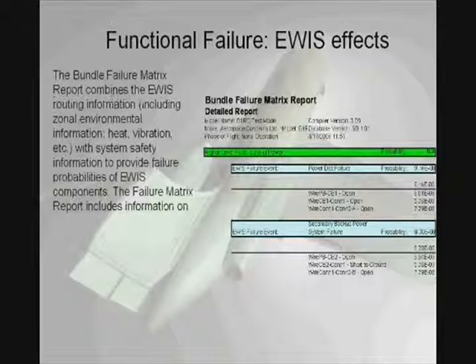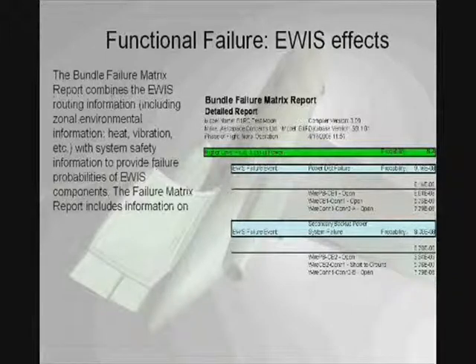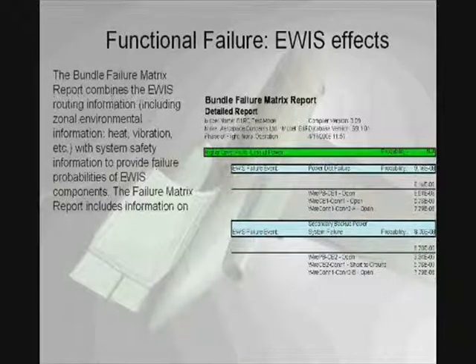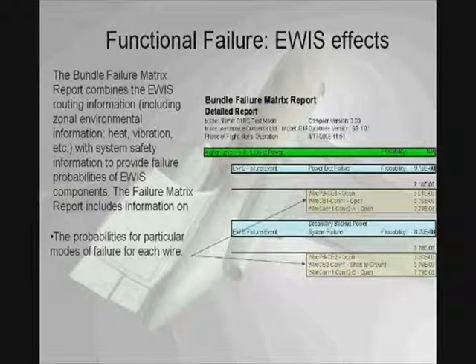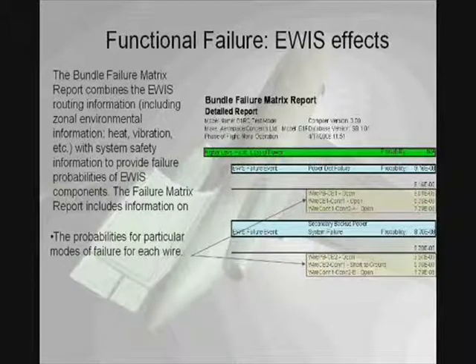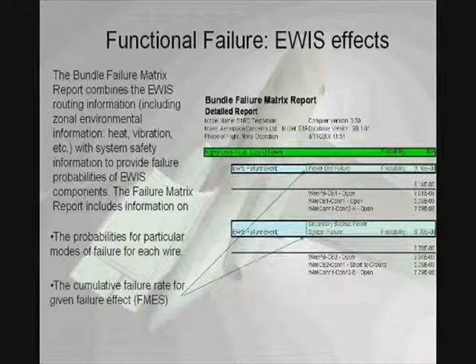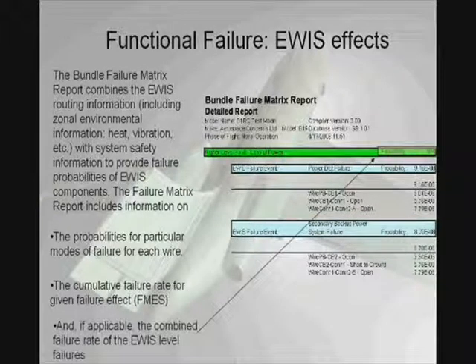The next step in the EWIS failure function analysis is the bundle failure matrix report, which combines the EWIS routing information — which includes information about heat, humidity, vibration, etc. — with the system information to provide the probabilities of EWIS component failure. The failure matrix report includes information on the probabilities of failure for a particular wire, the mechanisms for the failure, the cumulative failure rate for each given failure effect, which can be used in the FMES, and if applicable, the combined failure rate of the EWIS level failures.